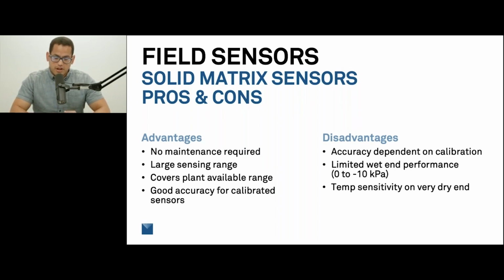Disadvantages: the accuracy is dependent on calibration, so you need to make sure you're getting your sensor calibrated or getting one that comes calibrated. Traditionally, they've had limited wet-end performance, but we've seen improvements with the Gen 2. In some cases we've seen temperature sensitivity because there's so little water held in the dry range, but we've seen improvements with methods for making those corrections, which we can touch on in future content.